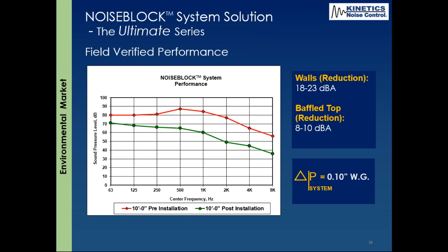On the top, holding a microphone 10 feet above and doing an array across the top of the pergola outside the enclosure, we were seeing an 8 to 10 dBA reduction. Across the system, upstream of the skirted wall louvers and downstream of the parallel baffles, there was only 1/10 of an inch water gauge pressure loss. Very minimal - that's key. If you can do that, the equipment can breathe properly, you won't void warranties, and you'll work well with the chiller manufacturer. The owner's going to be extremely happy, between the acoustical consultants working with Kinetics, our rep, the installers, and the chiller manufacturer.